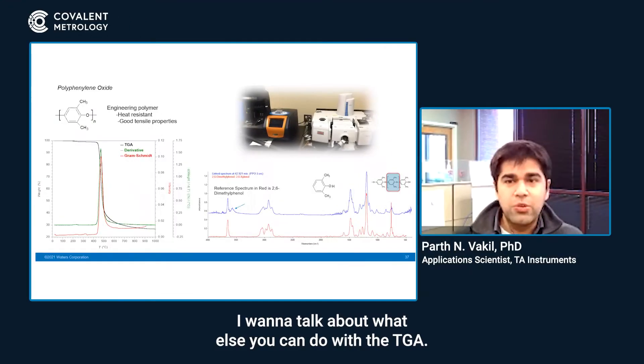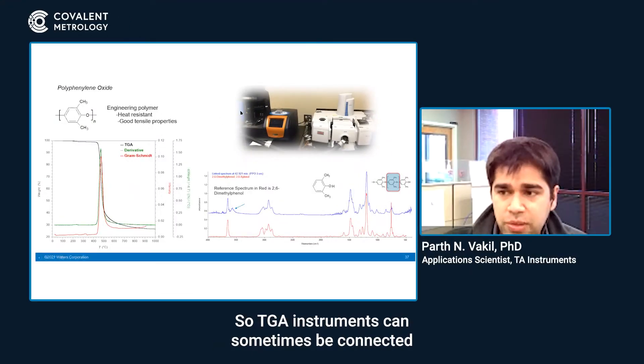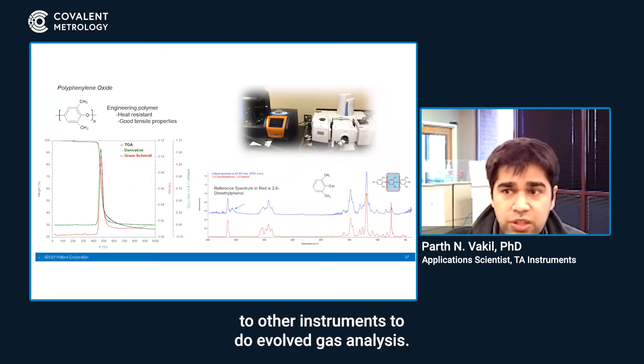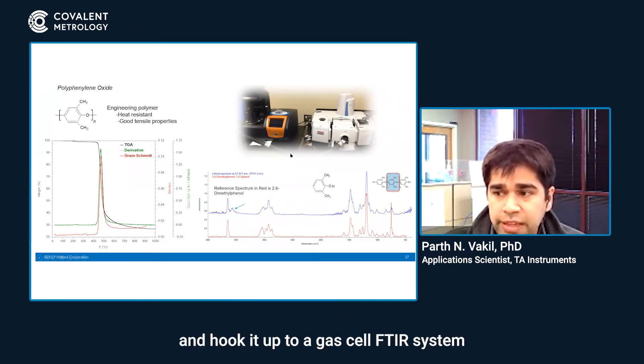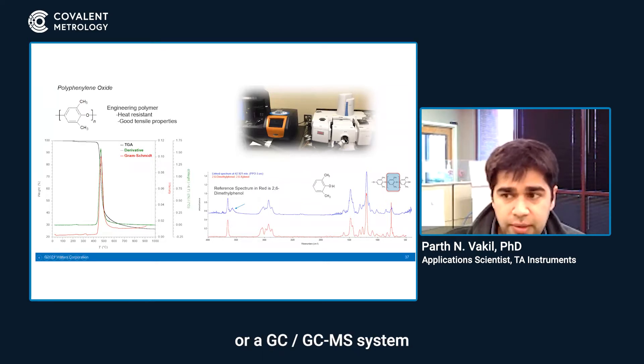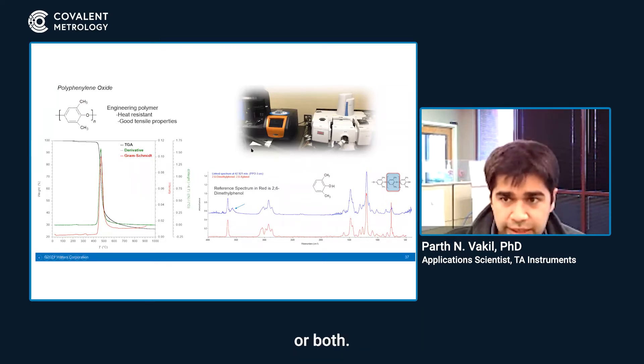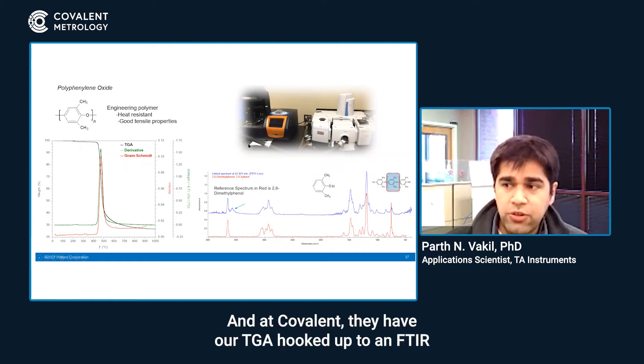I want to talk about what else you can do with the TGA. TGA instruments can sometimes be connected to other instruments to do evolved gas analysis. What I mean by that is you could take a TGA and hook it up to a gas cell FTIR system, a GCMS system, or both.